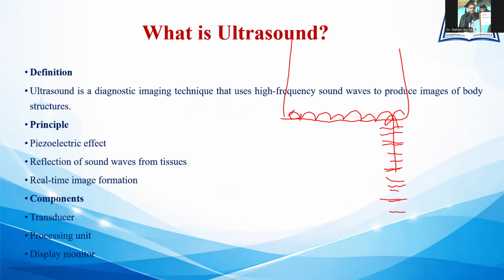the machine calculates the go-return time. Any structure placed near the transducer will have sound waves reflecting back with a short go-return time, while for any structure placed deep in the body, the reflected sound waves will have a greater go-return time. According to that go-return time, different reflectors are placed at different locations. Once the echoes are received by the transducer, the machine doesn't know anything about the structure, whatever it may be, human body or not, but according to the go-return time its location is placed, and the location of every structure is placed inside the body.